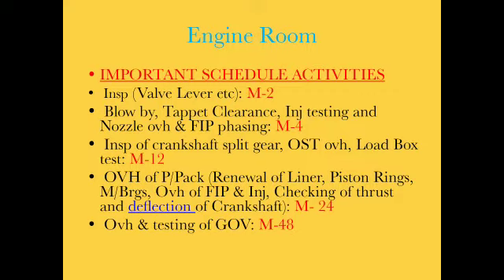Blow-by, tappet clearance, injection testing, and nozzle overhauling with FIP phasing at M4. Inspection of crankshaft, split gear, OST overhauling, and load box test at M12. Overhauling of power pack, renewal of liner, piston rings, and main bearings, overhauling of FIP, injection, and checking of thrust and deflection of crankshaft at M24. Overhauling and testing of governor at M48.